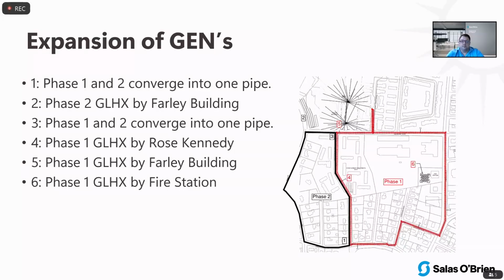So rather than digging up and replacing that entire section, creating two smaller 20-foot mix loop sections on each end and just replacing that section, and then modeling that to make sure we can still transfer enough energy within that 20-foot and see how that worked to see whether or not that was a good way to expand the system.